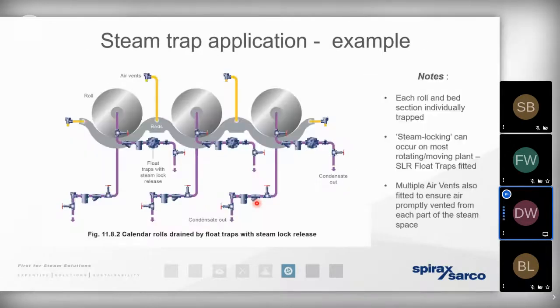So there are many different applications where traps are going to be used. For some processes, it's not unusual for us to require different types of steam traps at different areas of the process. They're going to have different functions. They could be moving condensate at different temperatures, pressures, mass flow rates, and they could be exposed to different criteria. The important thing is that we don't think of a steam trap as being a universal device. Each trap has to be sized and selected in accordance with each individual application.